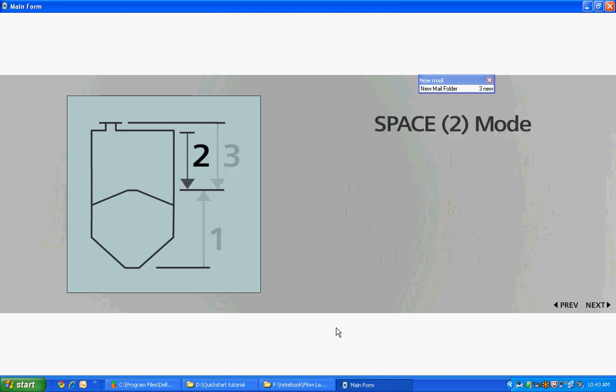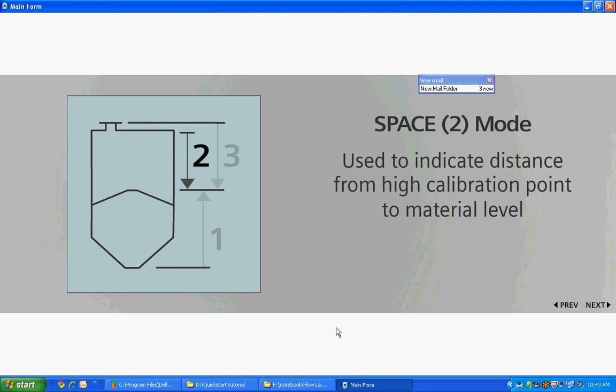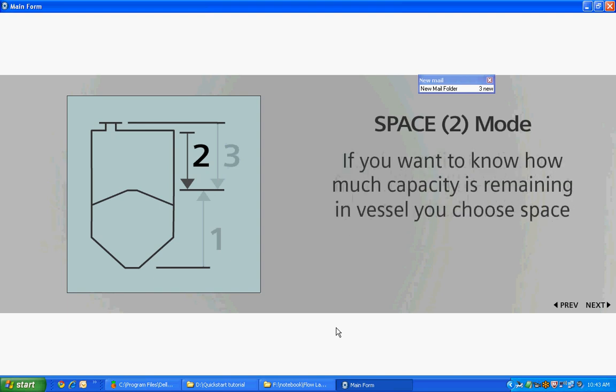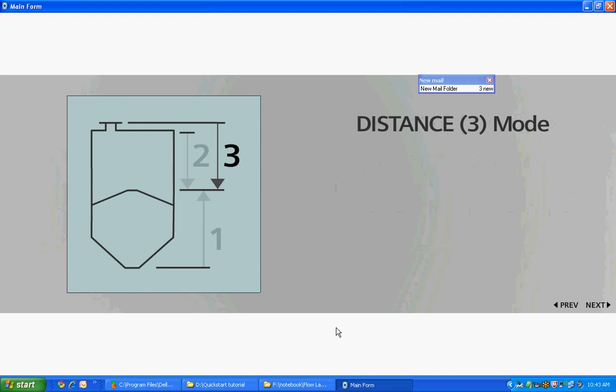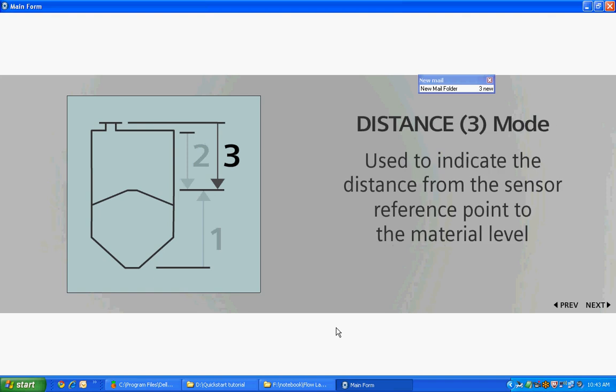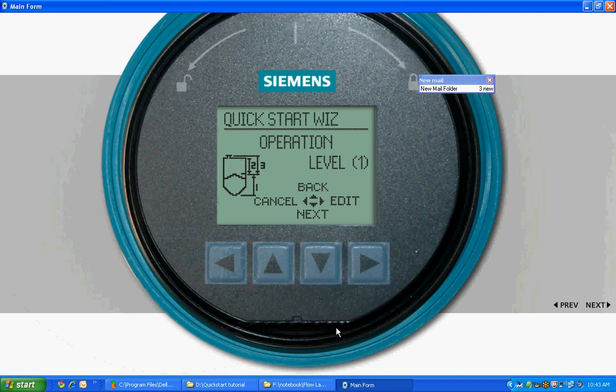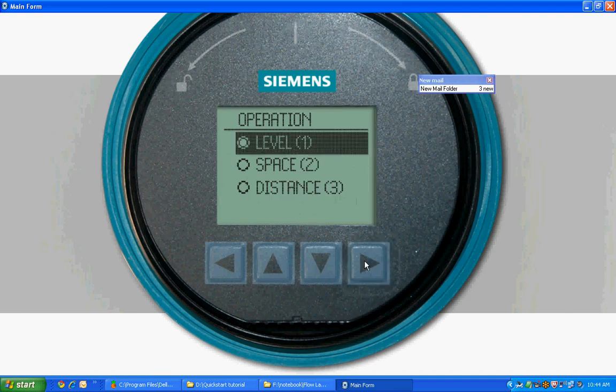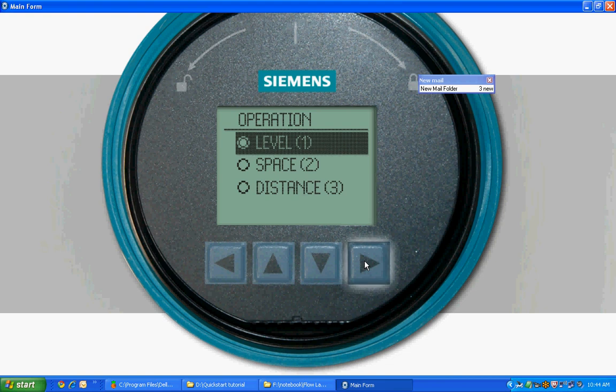The Space mode is used to indicate the distance from the high calibration point to the material level. If you want to know how much capacity is remaining in the vessel, you choose Space. The distance mode is used to indicate the distance from the sensor reference point to the material level. Press Edit to view options available. For this example, please select Level. Then press Right arrow to save your choice.